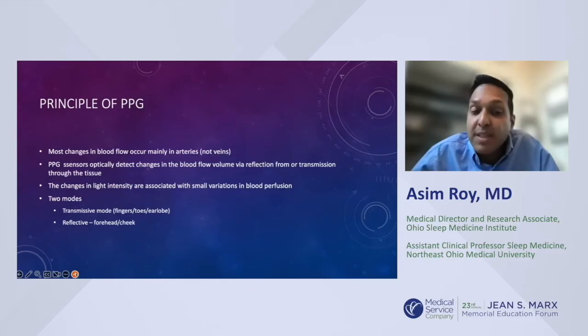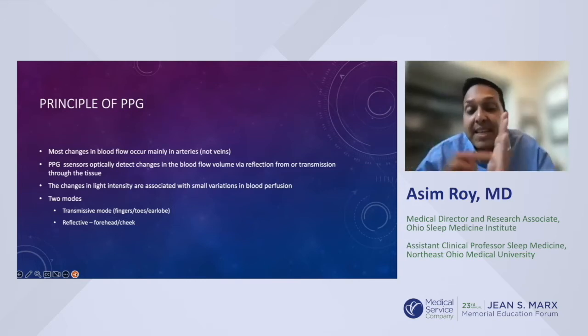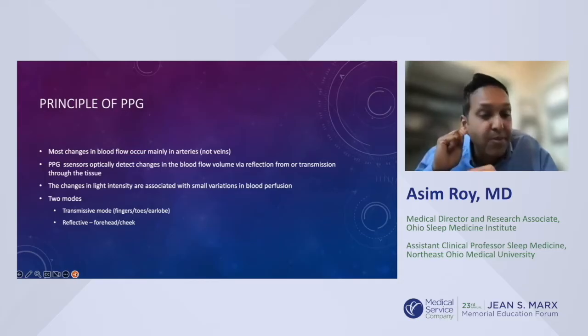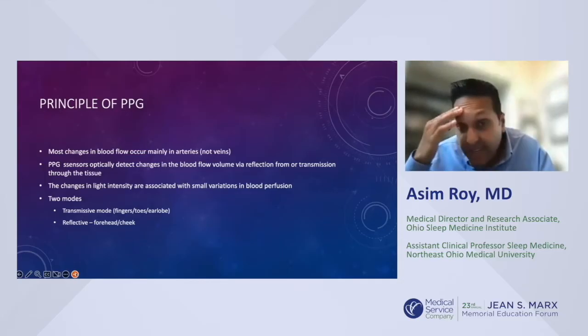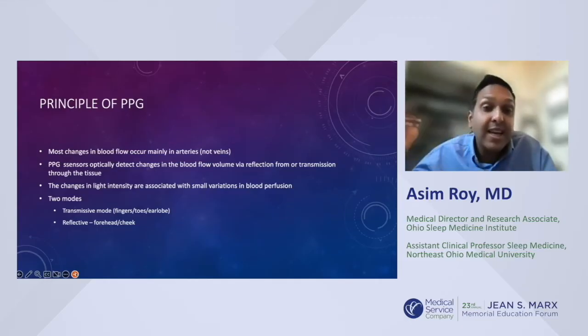The transmissive mode, commonly used at the finger, toes, or earlobe, requires light on one side and something to capture the light on the other side. That's why you have something on the front and back of the finger or on the earlobe. Reflective is typically done at the forehead or cheek - it's a one-directional light measuring the changes in volume.